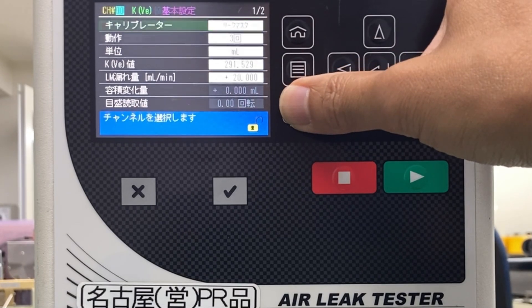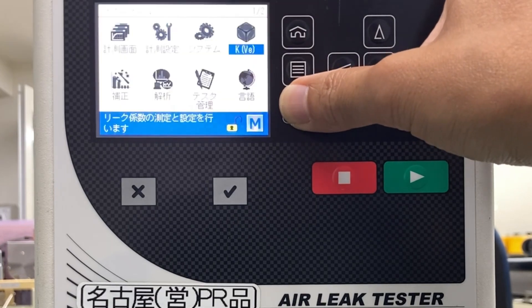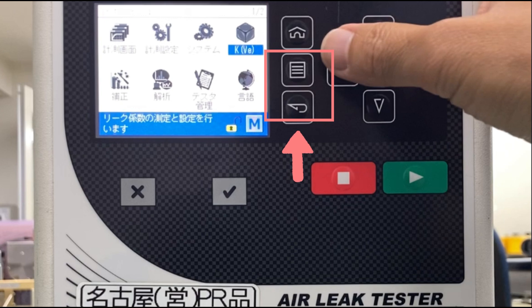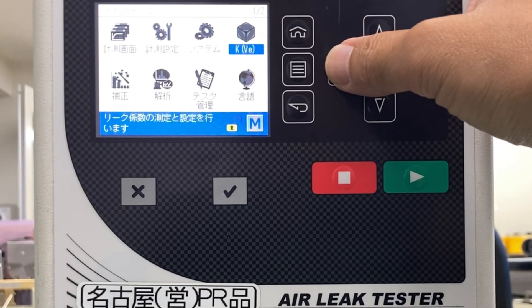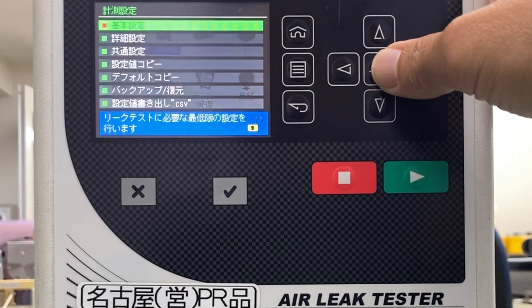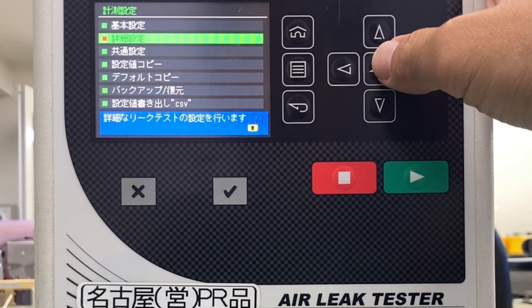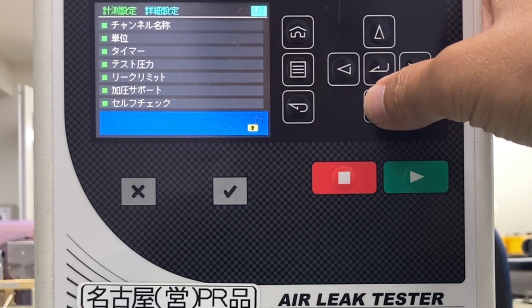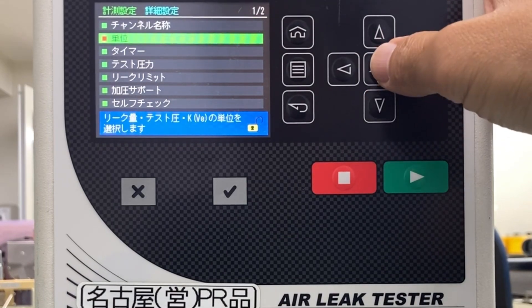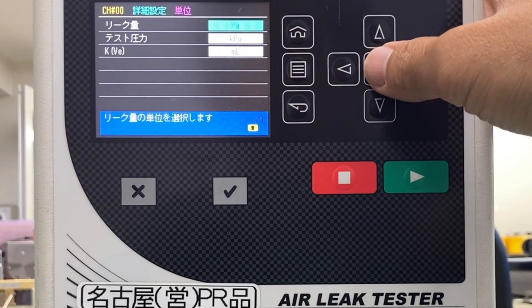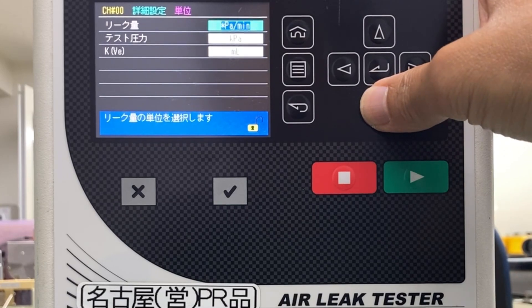Now that the KVE value has been measured, change the leak unit to a flow unit. Use the Back key or Menu key to go to the menu screen. Select Settings, then select Advanced Settings, and select the unit. Change the leak unit from PA to mL/min.